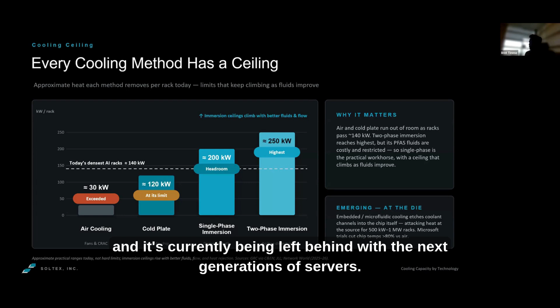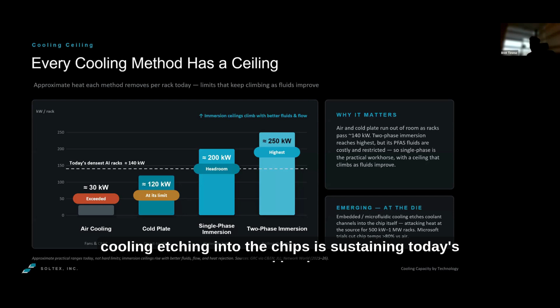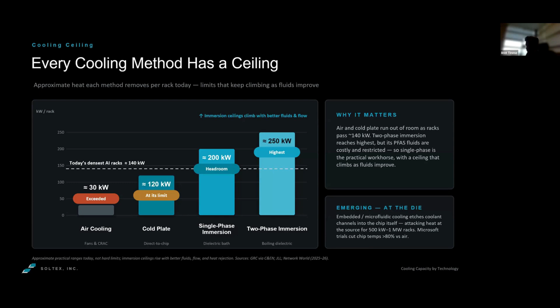Cold plate or direct chip gets you to about 120 kilowatts per rack, but is essentially at its limit against today's technologies. This, combined with embedded and microfluidic cooling etched into the chips, is sustaining today's workload, but it's hitting its limit.